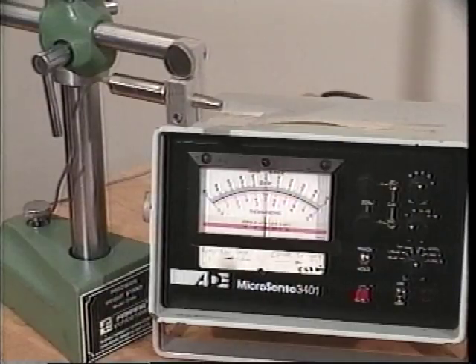Furthermore, the measurement range is only plus or minus 1/1000th of an inch. In addition, cap gauges are sensitive to contaminants on the target and probe surfaces, stray capacitance, and temperature fluctuations. Finally, it should be noted that although probing is non-contacting, a very small force is exerted on the target surface due to the associated electric field.